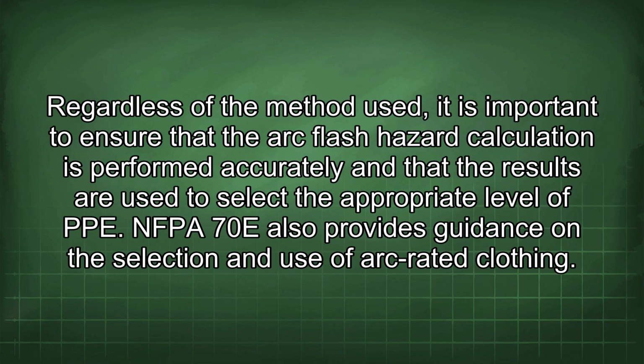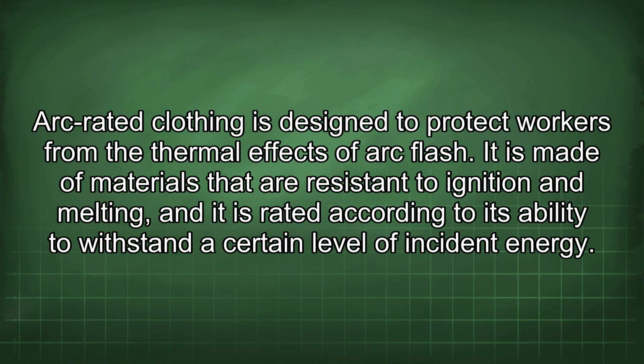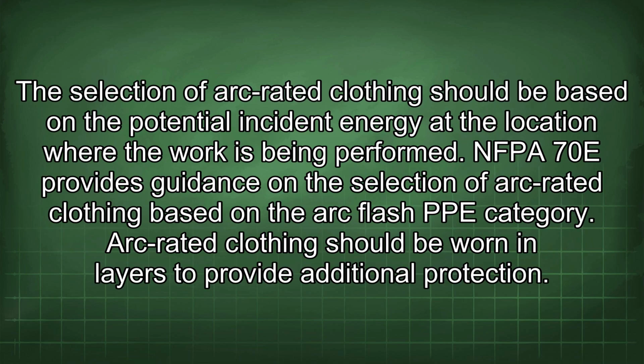NFPA 70E also provides guidance on the selection and use of arc-rated clothing. Arc-rated clothing is designed to protect workers from the thermal effects of arc flash. It is made of materials that are resistant to ignition and melting, and it is rated according to its ability to withstand a certain level of incident energy. The selection of arc-rated clothing should be based on the potential incident energy at the location where the work is being performed.